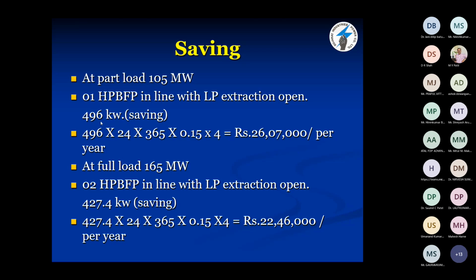The saving was 496 kilowatt. 496 into 24 hours into 365 days. Considering 4 rupees per unit, the saving was 26 lakhs rupees per year. And at full load at 165 megawatt, the saving was 22 lakhs 46,000 rupees per year.